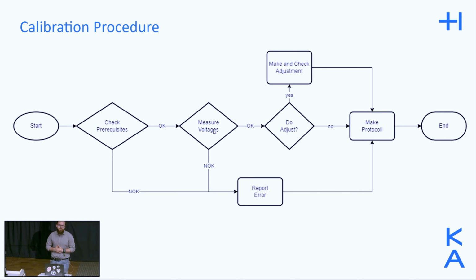There's a total of 15 measurements to be taken for each channel, so a total of 90 measurements. Then there's an option to write the adjustment values of the calibration back to the EEPROM of the data logger. That's optional. If that's done, in any case, the results of the calibration get logged inside a PDF protocol, which is dynamically generated at the end of the procedure, along with any errors that might have occurred, so you can debug them later.